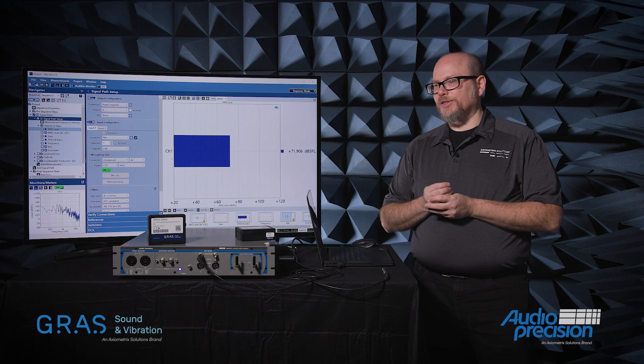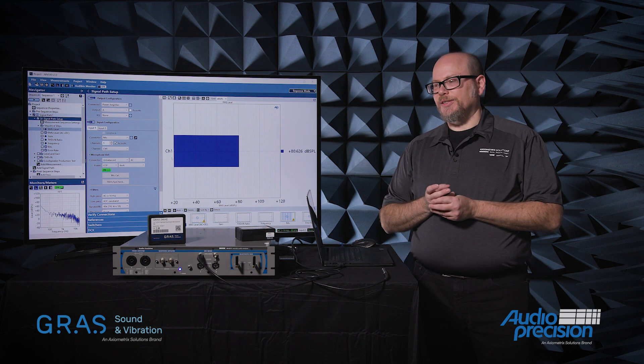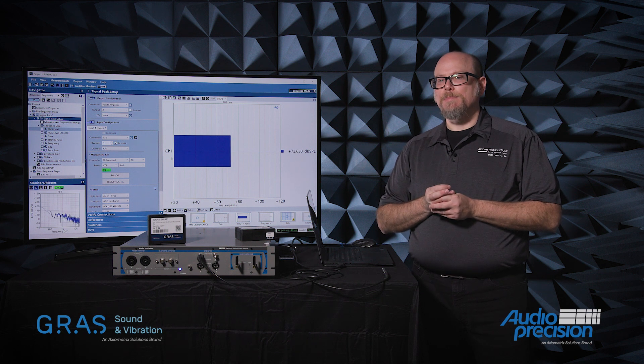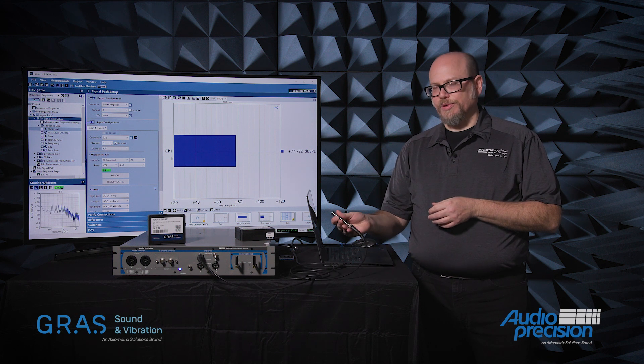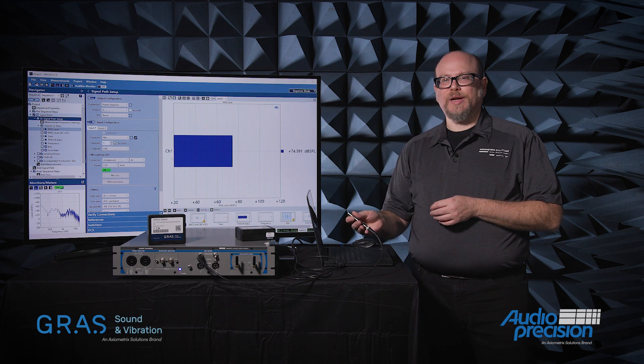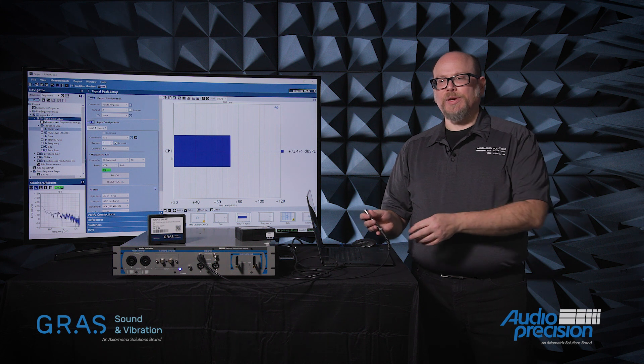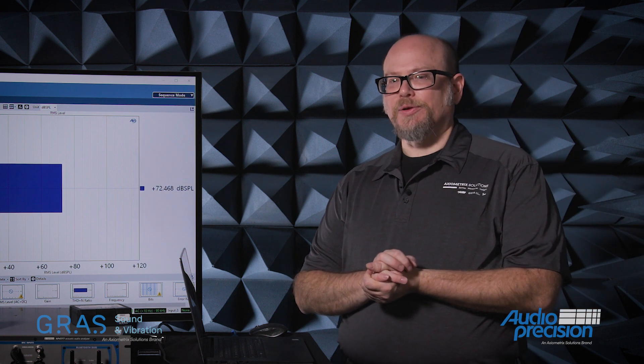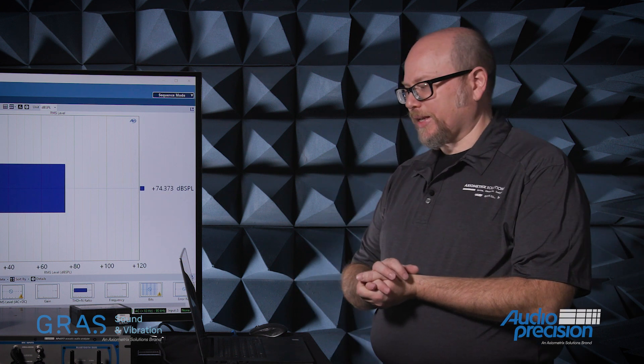The one downside to capturing it via TEDS is that TEDS has not actually measured anything. In this case, the microphone was calibrated at the factory in Denmark. The sensitivity information was programmed into the microphone, and we are simply reading that out. The next step, which is what I'd like to demonstrate today, is SysCheck 2. What SysCheck 2 allows us to do is actively verify that the sensitivity of the microphone has not drifted since it was last calibrated.